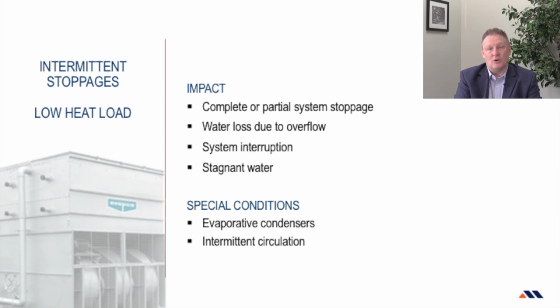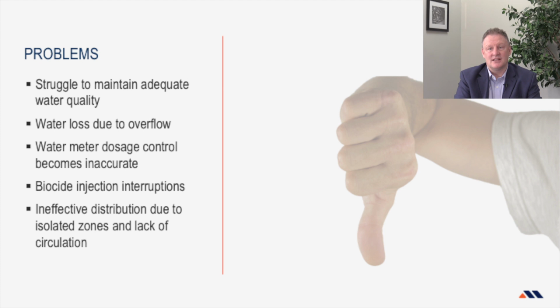Usually, there will be water loss due to overflow as discussed, and because the inhibitor is sometimes controlled to the bleed water meter, the inhibitor is no longer fed to the system properly, causing the inhibitor protection to be ineffective. The overflow of water will result in chemically imbalanced system. With no water circulation, biocide injections might also be interrupted, which could result in an uneven distribution since the isolated zones will be dependent on the treatment.